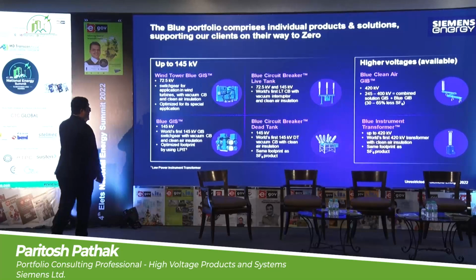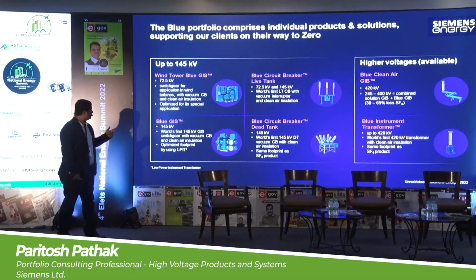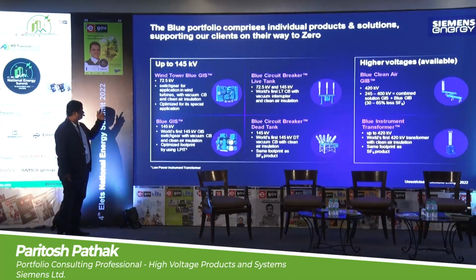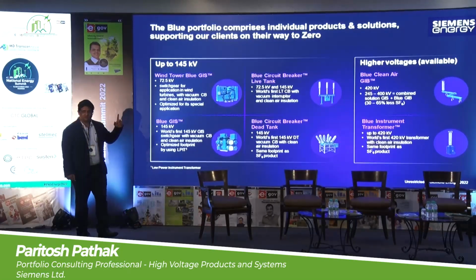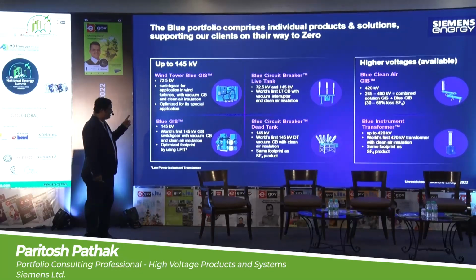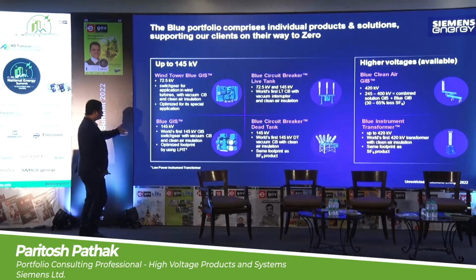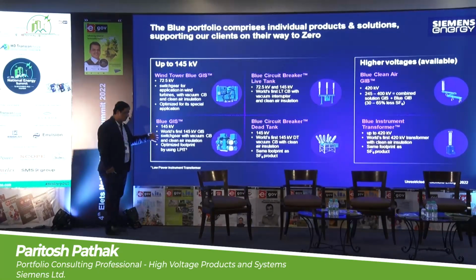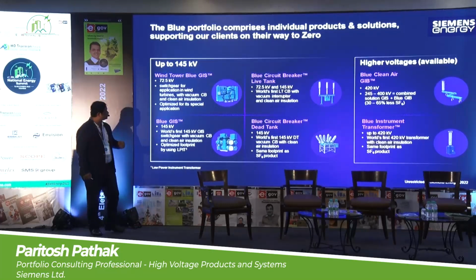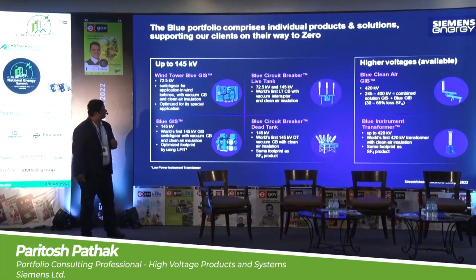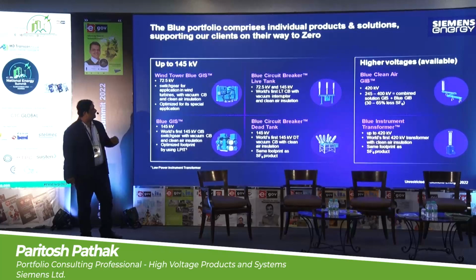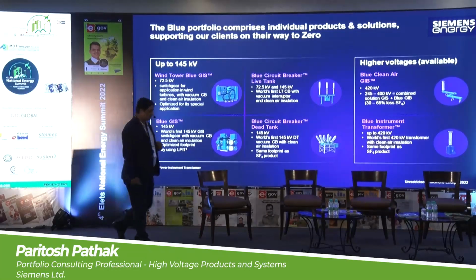This is the Blue portfolio from Siemens globally. We have developed the Wind Tower Blue GIS, a 72.5 kV switchgear application especially for wind, which can be used directly there. It's a combination of clean air and a vacuum interrupter chamber. The Blue GIS can also be used for normal operations. There's also the Blue circuit breaker, dead tank circuit breakers, and higher voltage variants.